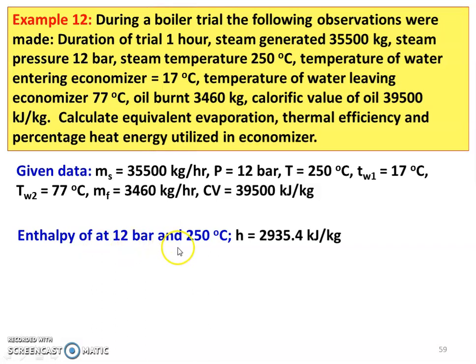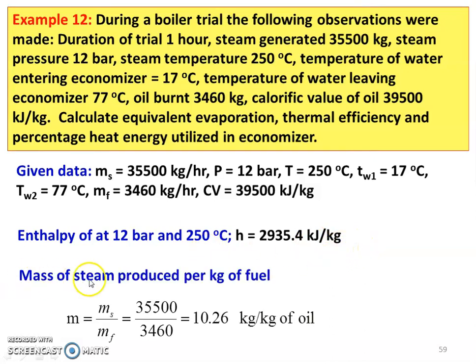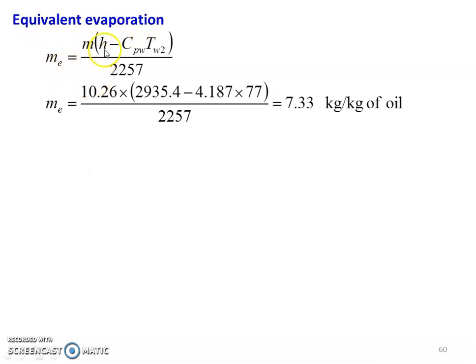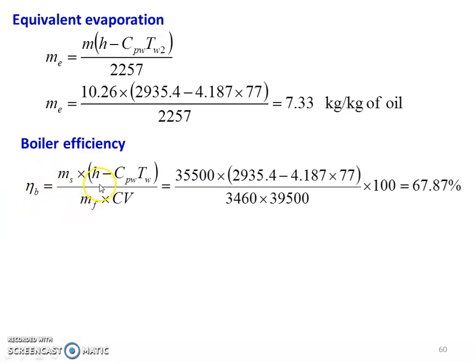The enthalpy of steam at 12 bar and 250 degrees Celsius: H equals 2935.4 kJ per kilogram — this data from the steam table. Mass of steam produced per kilogram of fuel: M equals MS divided by MF equals 35,500 divided by 3,460 equals 10.26 kg per kilogram of oil. Equivalent evaporation: ME equals M into (H minus Cpw into Tw2), where Tw2 is the temperature at the outlet of the economizer, divided by 2257. So, 10.26 into (2935.4 minus 4.187 into 77) divided by 2257 equals 7.33 kg per kilogram of oil. Boiler efficiency: eta B equals MS into (H minus Cpw into Tw2) divided by MF into Cv. So, 35,500 into (2935.4 minus 4.187 into 77) divided by 3,460 into 39,500 into 100 equals 67.87%.